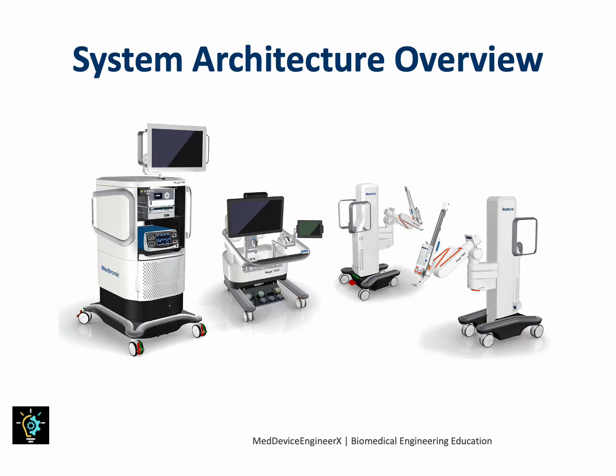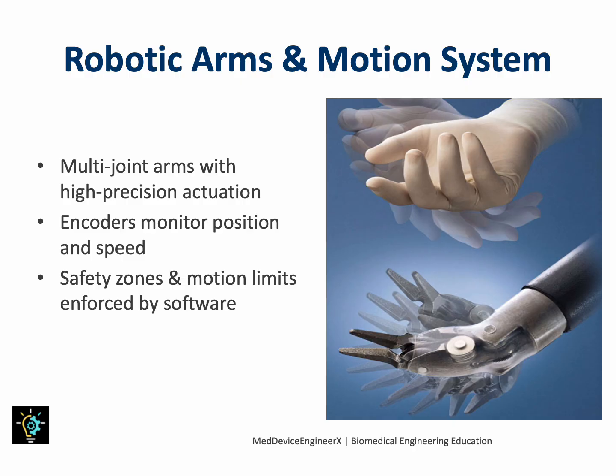The stop button is normally located in here, and this would stop the system. The robotic arms are the center of the Hugo platform. Each arm contains multiple joints driven by high-precision actuators, typically brushless DC motors paired with harmonic gear mechanisms. These provide smooth, controlled movements with very low backlash, which is essential during delicate procedures.